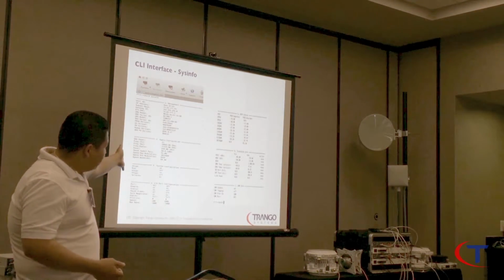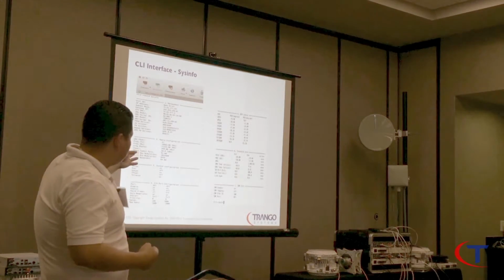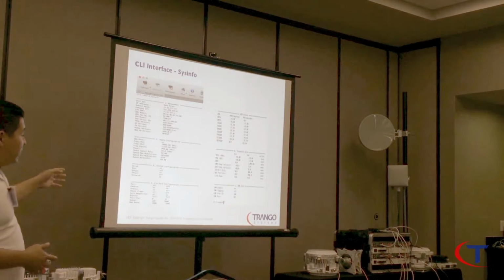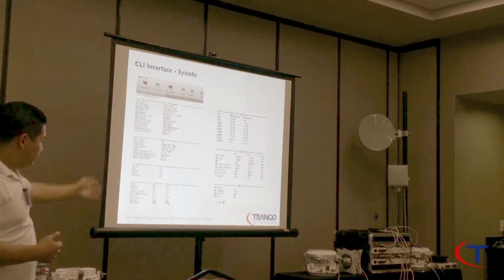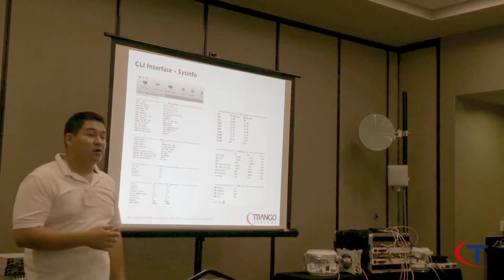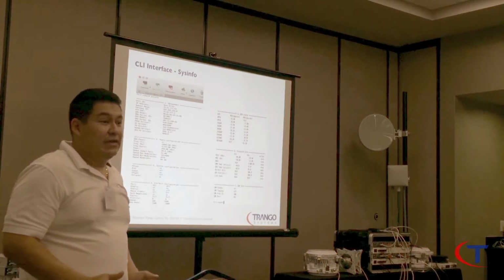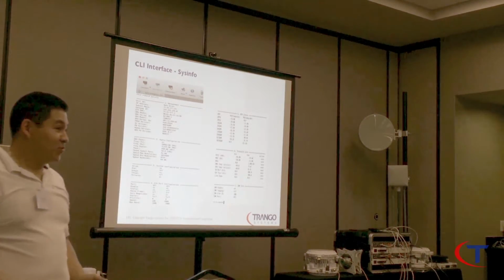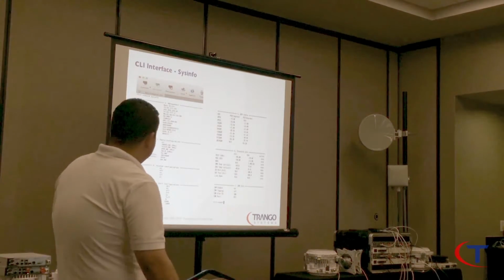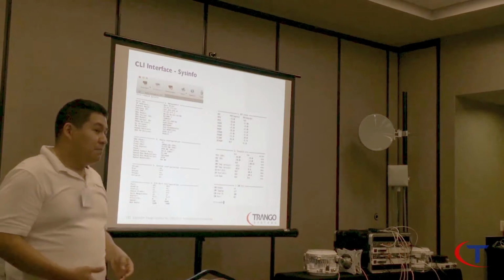Radio configuration: ODU power on or off, frequency duplex, our transmit frequency, receive frequency. Everything from the web interface is here as well. System configuration. HTTP, it's on. If I turn it off, you must go via the CLI. Okay, you cannot access the web. That may happen to you once in a while. PLA. If you're not using PLA, it must be off.